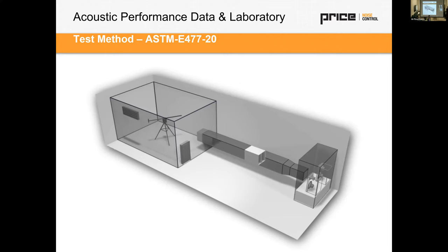One of the big things I want you to be aware of is that we test to a very specific standard, this ASTM E477 standard. That's the standard that's written for measuring and testing silencers. One of the interesting facts is that the dash at the back of this standard has changed many times over the last 30 years or so, and the latest was in 2020, which you can see denoted by dash 20. I'm going to talk in detail about that standard and what's changed on it, most recently with the 2020 revision. But just be aware at this point that the ASTM E477 standard is an important one with respect to noise control and sound.